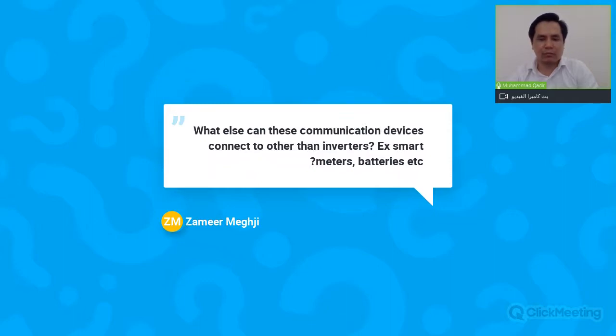The second question: what else can these communication devices connect to other than inverters? For example, smart meters, batteries. It depends. The inverters themselves can connect only with the devices mentioned in this presentation, but the smart logger you can connect to other devices as well, such as power meters, analog temperature sensors, and weather stations. And if you have any specific requirement, just send it to us, and we will see whether connectivity is possible for that device with this smart logger or not.